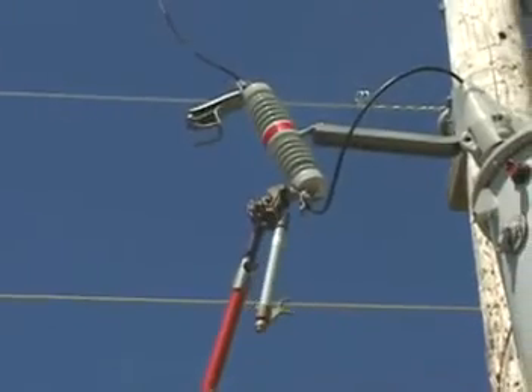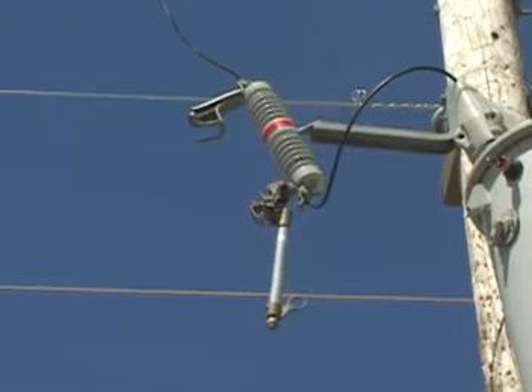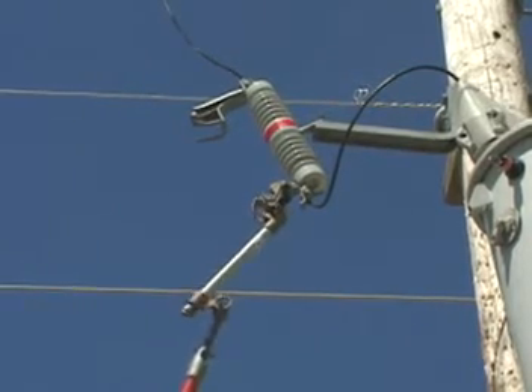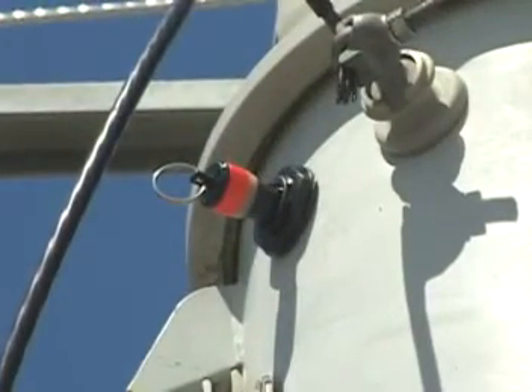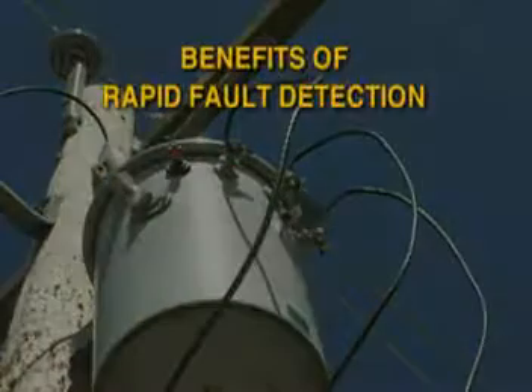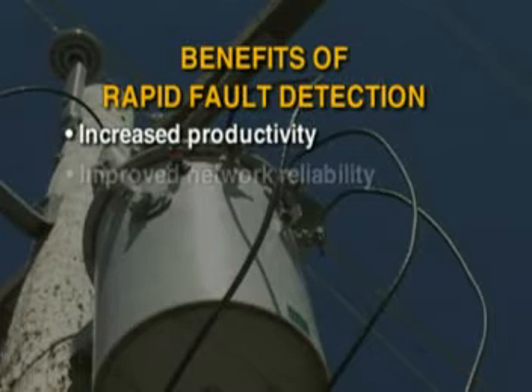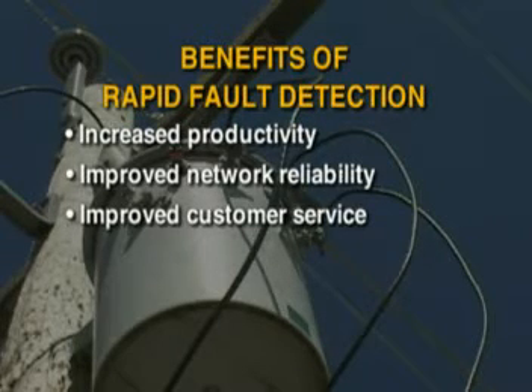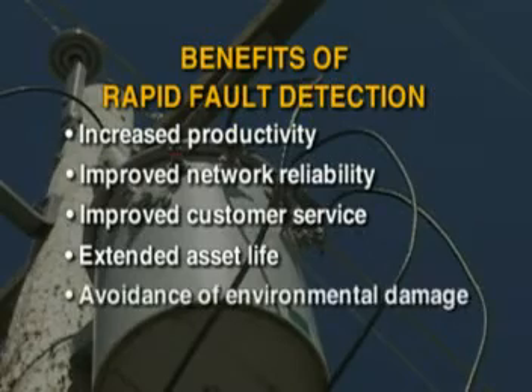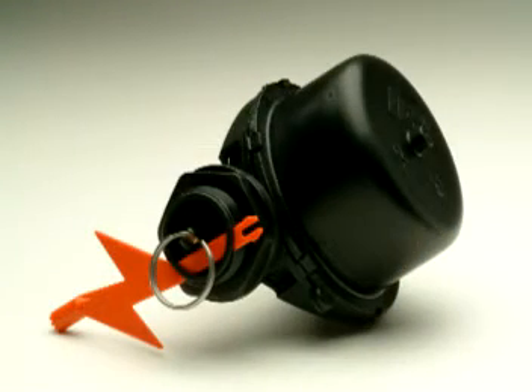So to recap, according to industry studies, 1 in 5 transformer re-energization operations involves a transformer with an internal fault. The IFD will display a highly visible flag indicating which transformers are faulted. The benefits in the rapid detection of these faults include increased line crew productivity, improved network reliability and customer service, extended asset life, avoidance of environmental damage, and of course, increased job safety. As modern utilities strive to continually improve the efficiency of supply networks, the IFD is the next key implementation to enhance the performance of your distribution infrastructure.